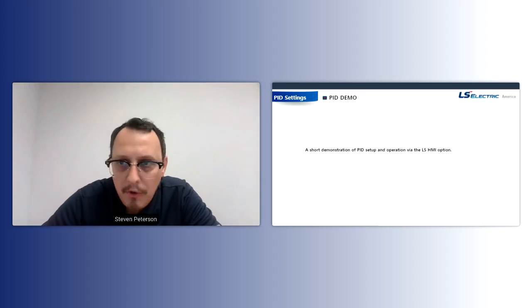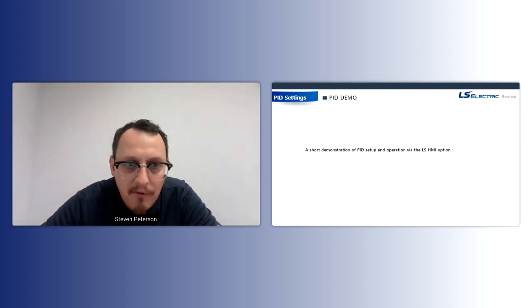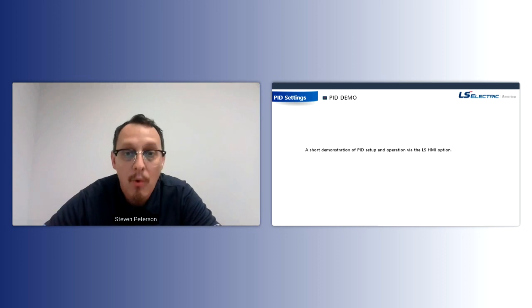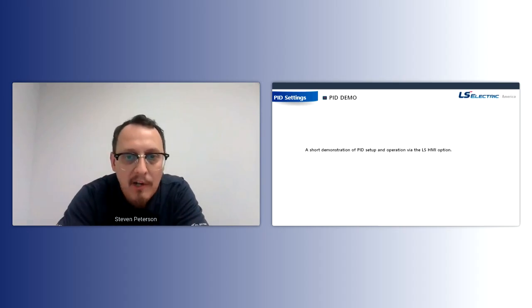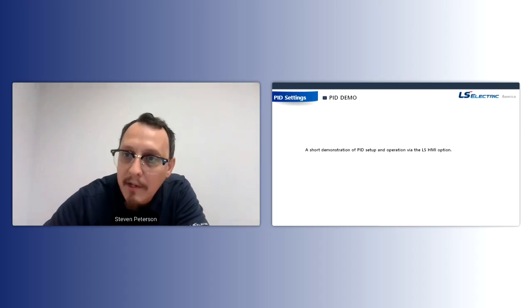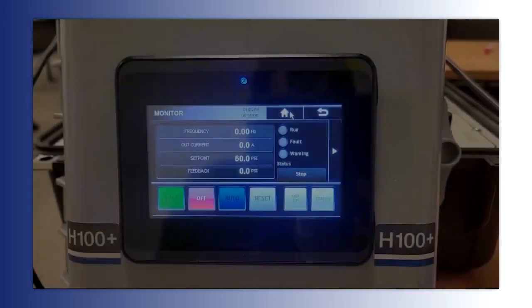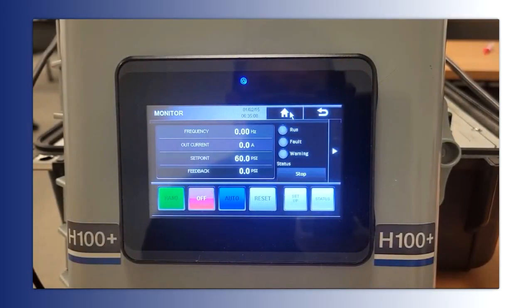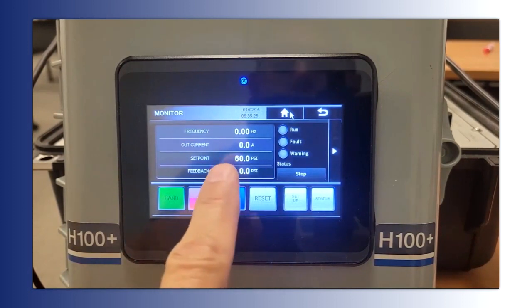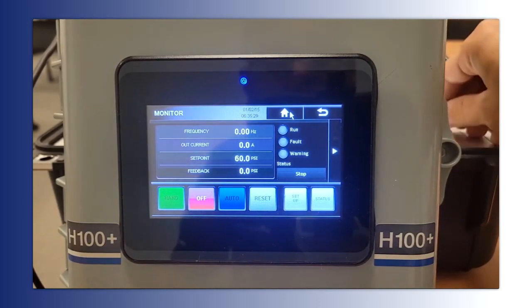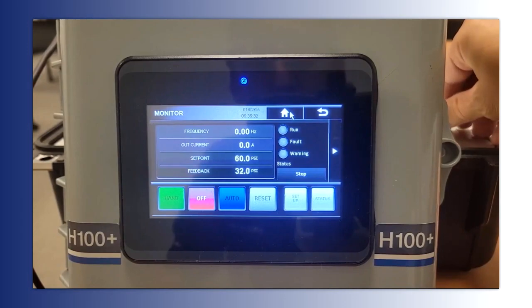Okay. So the next thing I have here is a short 5-minute demonstration that shows PID setup and operation. What we're doing is using one of our other automation products, which is the LS HMI. So I'm going to go ahead and start this video. So right here we have the LS HMI connected to the H100 Plus, which is the drive we're talking about. This drive's been programmed via the pressure control macro that we also discussed. You can see here we have access to our set point, we have our feedback, and I have a demo right behind this, so I could simulate my feedback going up and down.